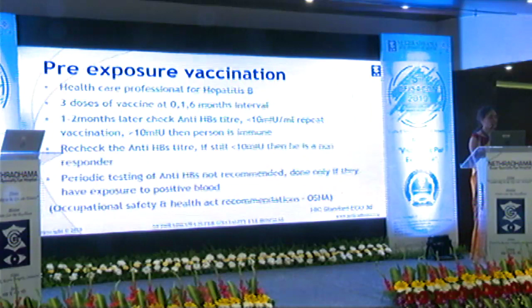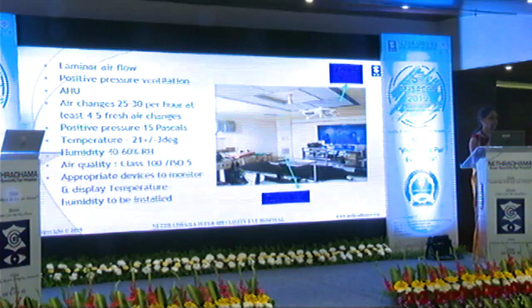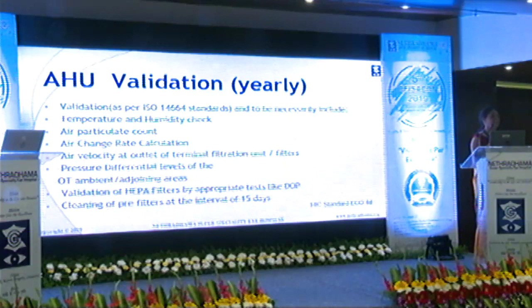As mentioned earlier, the air handling unit is very important for all hospitals, including for eco standards. Guidelines require at least 25 air changes with 4 fresh air changes, with temperature maintained, and the AHU validated yearly.